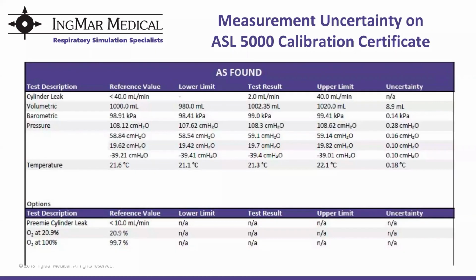Here's the back of our calibration certificate, our ISO 17025 calibration certificate. As you can see, the uncertainty listed on the calibration certificate for the test result of 20 centimeters of water comes directly from our measurement uncertainty budget from the previous slide. And every uncertainty listed on our calibration certificate has a measurement uncertainty budget that is approved by our accreditation provider before we can issue it on the certificate that is provided to the customer.